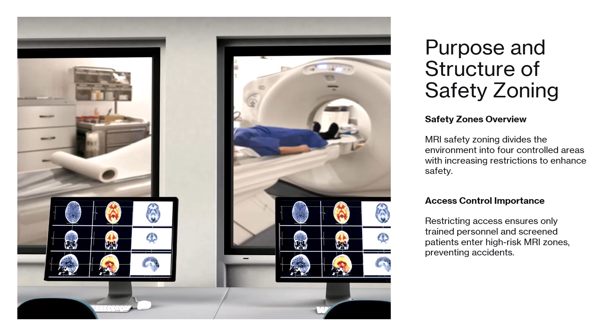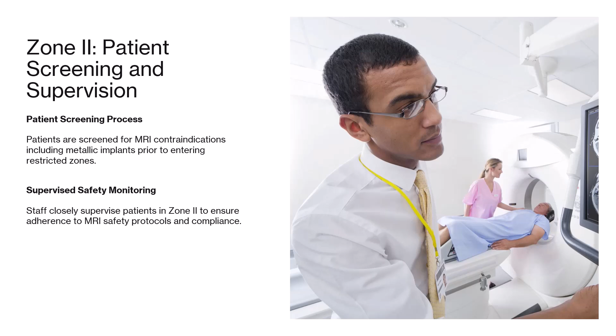Zone 1 is the freely accessible area outside the MRI environment, such as reception or waiting rooms. It poses no magnetic risk and is open to the public and hospital staff without restrictions. In Zone 2, patients are screened for contraindications to MRI, such as metallic implants or devices, before entering controlled zones. Staff closely monitors patients here to ensure safety and compliance.